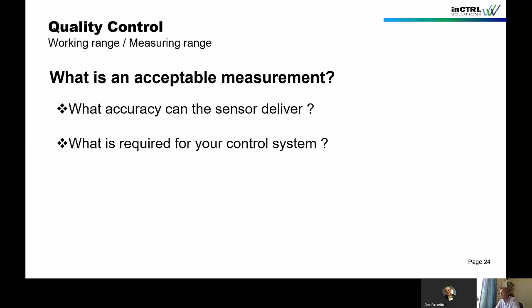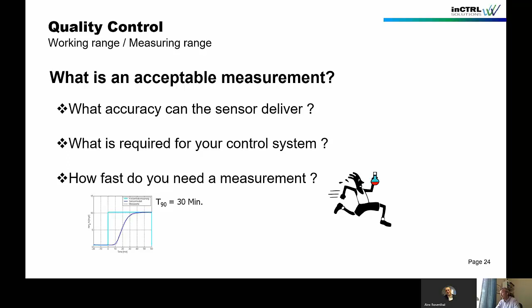What makes it tricky is that typically there are two groups involved, right? So you have the instrumentation staff, and then you have the process operators and engineers, and they have to communicate and get together, right? And that is, at times, quite a tricky bit. Very important actually is to be able to properly quantify both sides, because only then you can come to a conclusion or a solution. Last question is, how fast do you need a measurement, right? So that is the response time, and that is important for control system design and tuning, right? So very important information for your control people to know how long it takes to get the measurement, right? So that may change the tuning completely or make it impossible to get that control system to work.